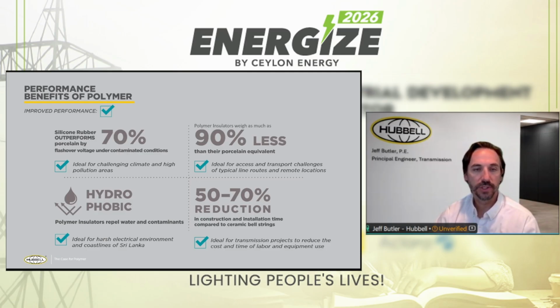I mentioned the hydrophobicity that is able to improve performance, especially in a country like Sri Lanka. There's an extensive coastline, being an island, so I imagine that there's a lot of salt spray, salt contamination, coastal environments where the hydrophobicity characteristic of silicone rubber would be advantageous. And then furthermore, in installation and construction costs, we've talked to contractors that can see a 50 to 70% reduction in the time needed to install polymer insulators as compared to ceramic equivalents.